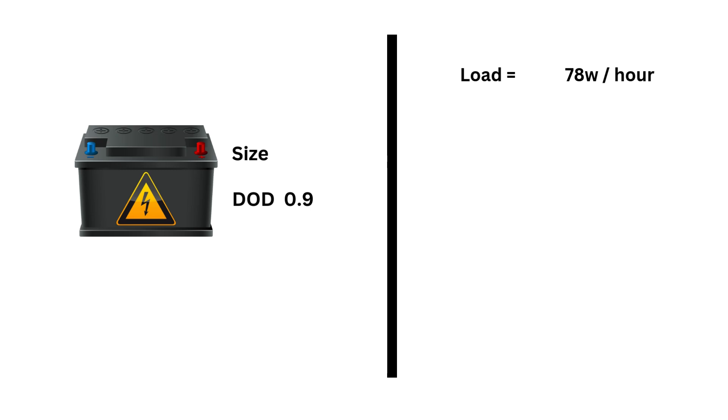Let's consider our battery size and depth of discharge, or DoD. We have here a 12 volts 50 ampere hour battery bank. We have to calculate its energy rating in watt-hours because this calculation requires us to divide battery energy rating by total power or load going on the battery bank to get the accurate run time. Battery voltage of 12 volts multiplied by its current of 50 ampere hours equals 600 watt-hours.